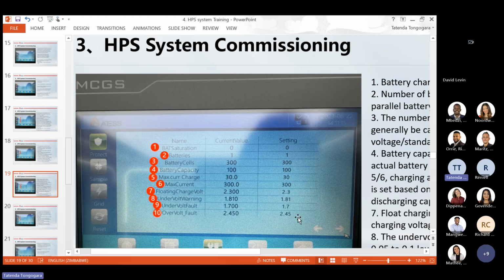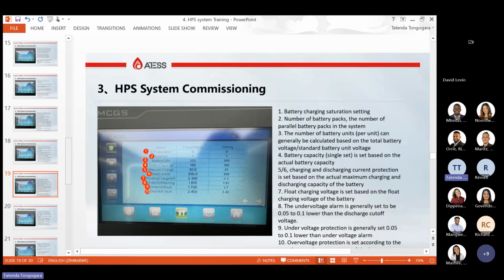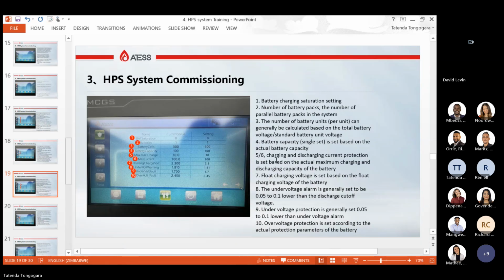And then we have overvolt fault at this value. So if your overvolt value is 3.6 and your battery charge goes beyond 3.6, the system will go into fault mode. And then we also have undervolt warning. And then float charging is based on the float charging voltage of the battery. These battery values you get from the battery manufacturer or inside the manual of the battery, but some manufacturers don't write this for you. So if you are not sure, contact us, because if you put a wrong value here, your system will not work.